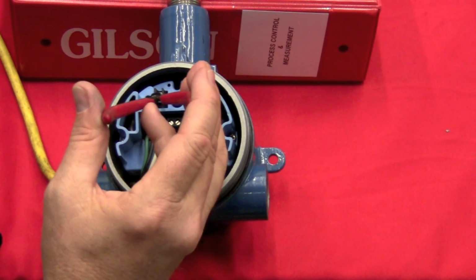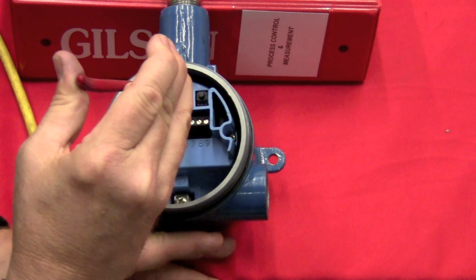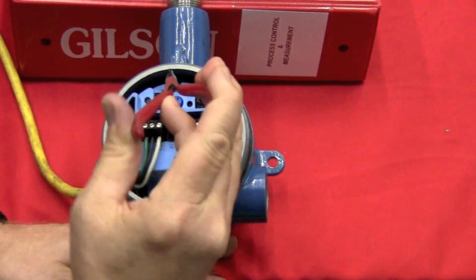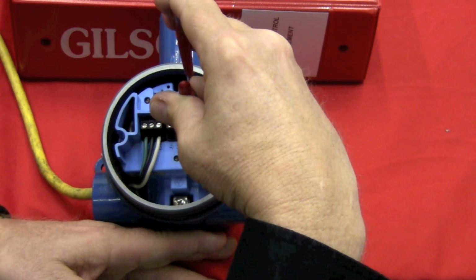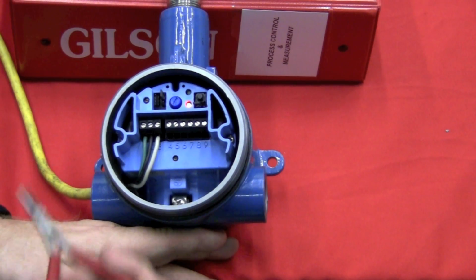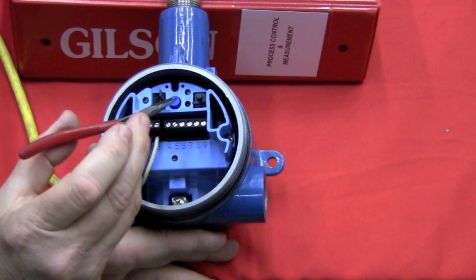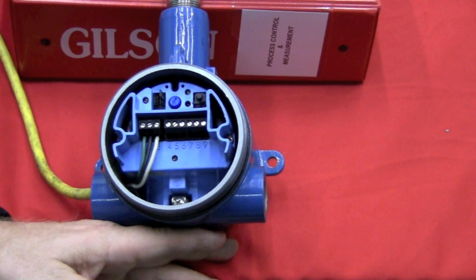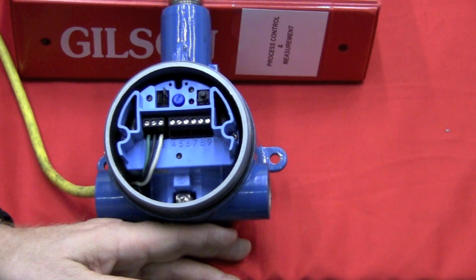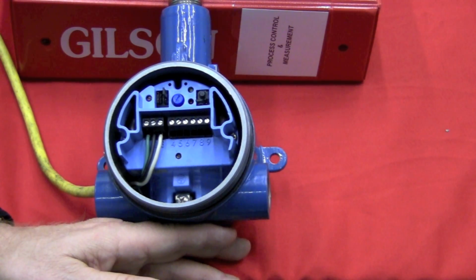To go into the calibration mode, you take this time delay jumper off, and you put it on the pins 1 and 2 next to the cal button, and you'll see that our green power LED went out, and the red is beginning to flash. If you just watch the red LED, you'll see that it flashes 4 times, and then there's a pause. It'll flash 4 times, and then there's a pause. That means that this unit is in mode 4.